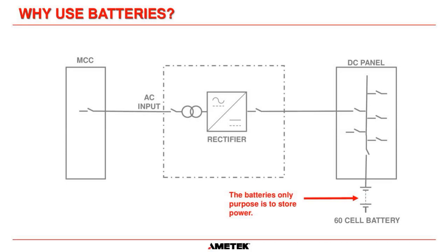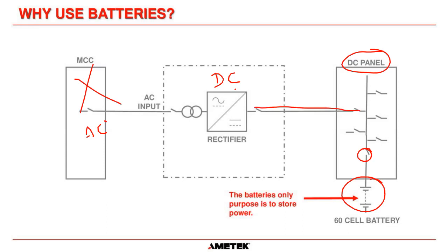So in this drawing here, this goes back to a typical charger DC system. We've got our AC going in here. This rectifier converts it to DC, and then that goes out to our DC panel. The only reason the battery is here is for storing the power if we have a failure on our AC input. In truth, don't ever do this, but you could run with this disconnect open and the battery disconnected, the AC getting converted to DC. It will feed the DC panel and it will keep your loads energized. But you need to have this battery backup if there is a power failure.